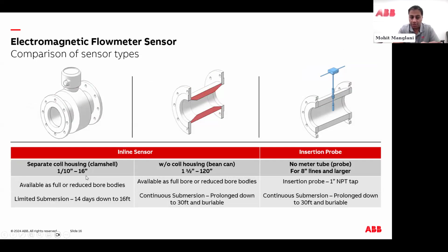This clamshell housing, you can put it underwater for 14 days, down to 16 feet continuously. Without a coil housing, where you don't have the clamshell design, you can put it underwater down to 30 feet and it'll last underwater forever, assuming you don't have any other events. And then the third type of meter is called an insertion probe. Imagine a 1-inch NPT process connection with a mag meter on the tip. We call this a mag on a stick.